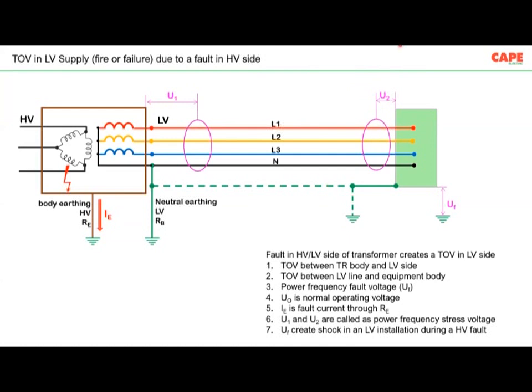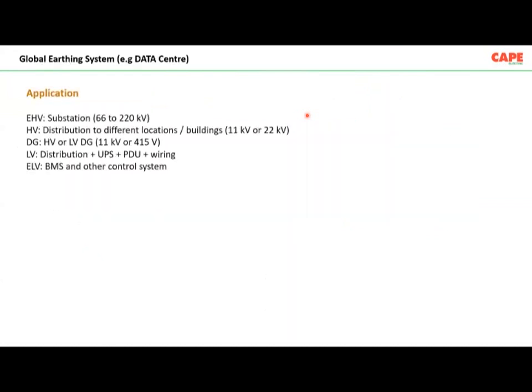Three problems, as I said. One is your transformer may fail. Anyway, it's outside. You don't need to bother. The second is that most of the time your equipment may fail. The third problem is you may get a shock. A person who is touching some part, let us say somebody touching the refrigerator, will get a shock. RCDs are not practically possible. RCDs will not work under this particular condition. So earthing actually has very, very important roles to limit the temporary overvoltages and shock voltages inside your equipment.